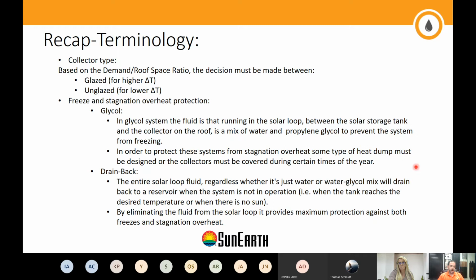So what's happening here is the heat is being stored in the solar storage tank, and once you reach this target heat in the collector, or the high limit or the low limit on your array, the entire loop will drain back into the main storage vessel. Here the heat is being extracted by 3 coiled heat exchangers submerged into this, and in order to avoid any pressure drops, we don't want to mess with the building's main flow rates, any of that stuff, we have a heat injection pump here operated by your solar thermal controller, injecting the hot water back to the main loop that goes into your boiler. That way you don't have to be worried about any pressure drop.